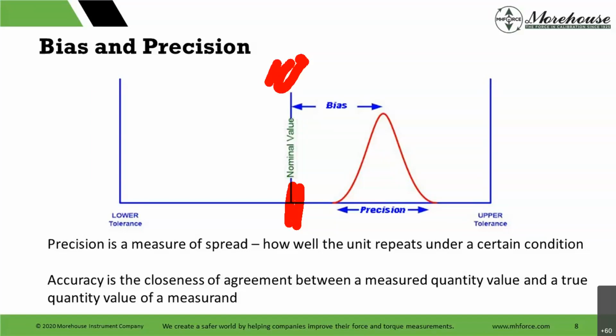Most people just look at this. But when we start looking at precision here, we're looking at the measure of that data. How well does that unit repeat? So if we just say accuracy, and I think I touched on this last week, there are manufacturers out there that will say, hey, I have a high reading, I have a low reading, and I'm going to take the average to report my accuracy. That tells you nothing about the repeatability condition, which is often the precision of the instrument. And we know a lot of people do this. The saying is, I can have my head in an oven and my feet in an ice bath, and on average, I can feel fine.